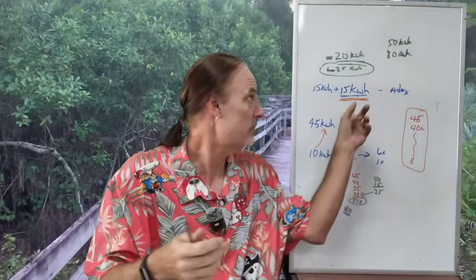The nice thing about that setup is I'm not running the generator 24/7. I run it at maximum efficiency for an hour or two to charge the batteries up to 80 or 90% of capacity all at once, then shut it off. I don't have to run a generator for several days until the batteries get low again. It's a much more efficient way of doing things.